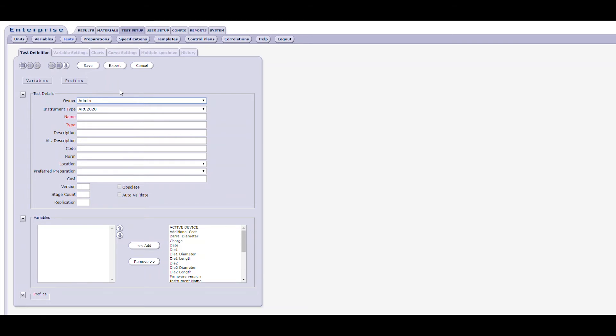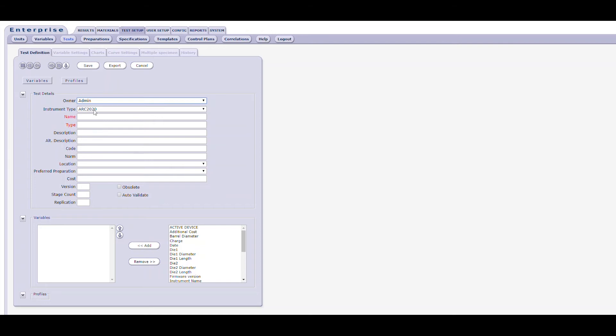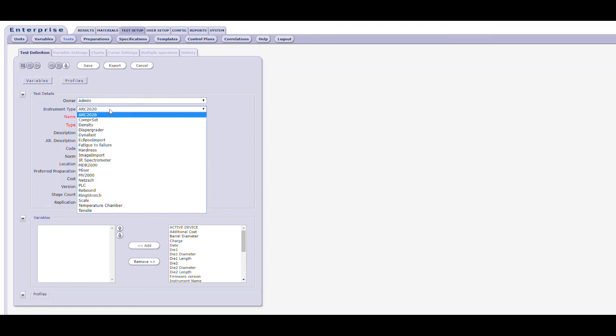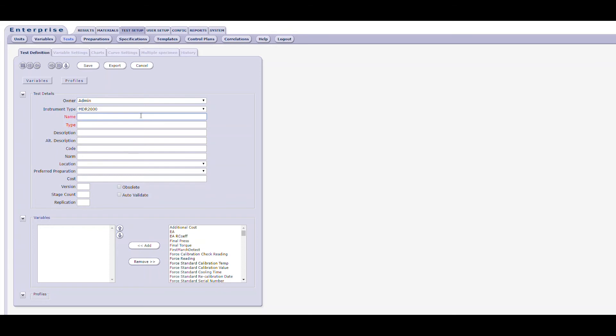Working from top to bottom, the test definition form will first present you with drop-downs for the owner of the test and the instrument type. Note the color of the field titles. Those in red are required fields, and those in black are optional. Your own needs will determine how many of the fields you will utilize. Below, owner and instrument type drop-downs are a series of text fields topped by the only required fields on this form, the name and type fields. The name field can hold up to 50 characters, and the type holds up to 80 characters. Entering information in these two fields will allow you to save the test and enable the other forms. So, we'll set the owner to admin, set our instrument type to an MDR2000, set our test to a Cure, and the type will also be Cure.